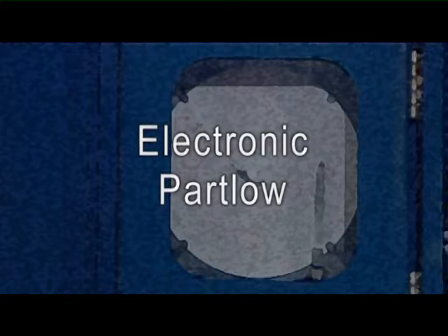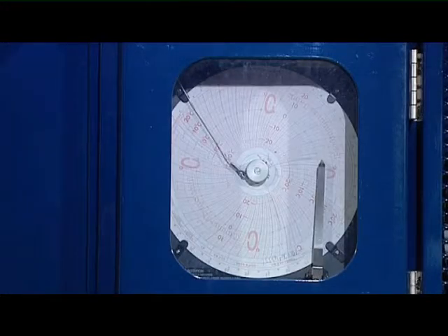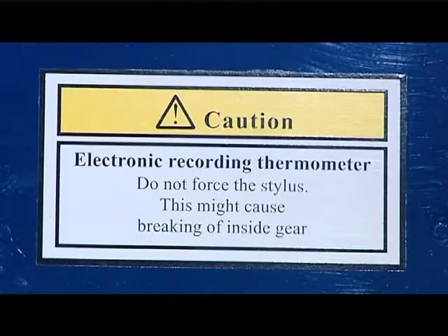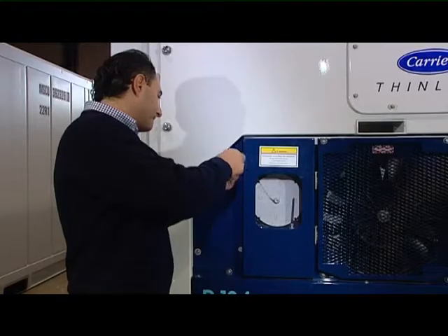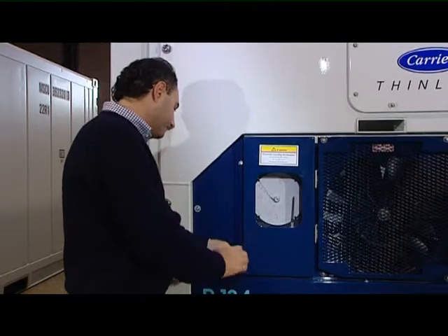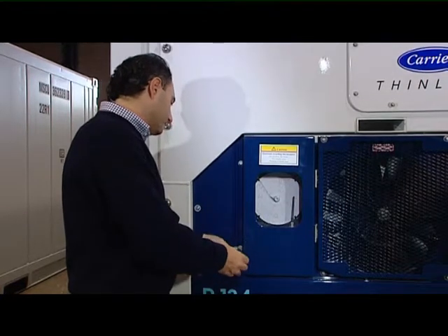Electronic Partlow. The Electronic Partlow automatically records the return or the supply air temperature depending on the set point. The recorder reads and records data from the controller. It can be compared to a printer. The recorder will stop when the power is switched off.